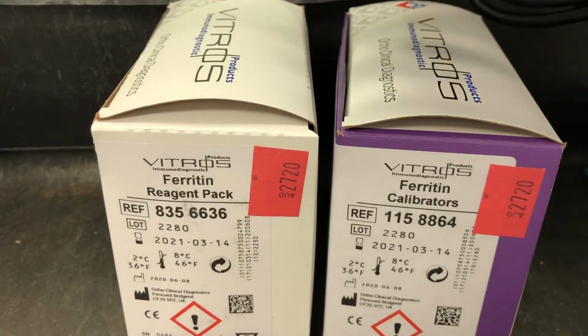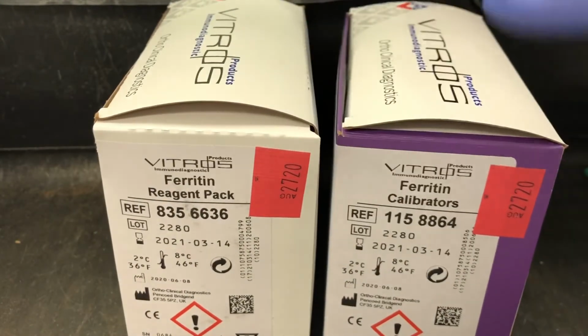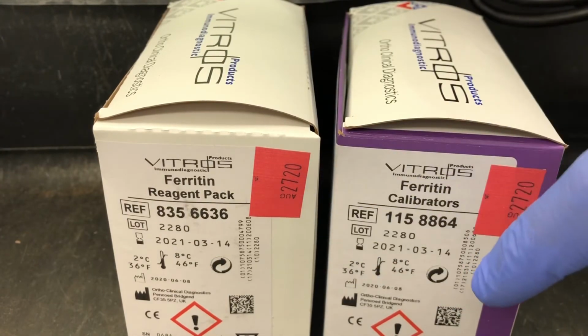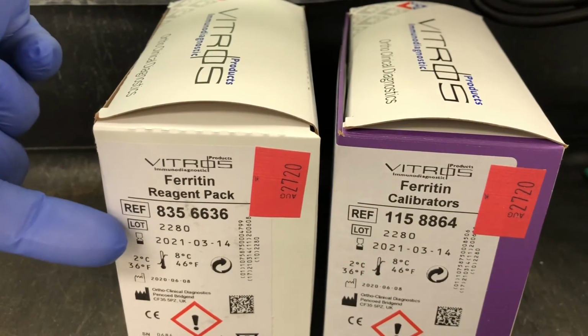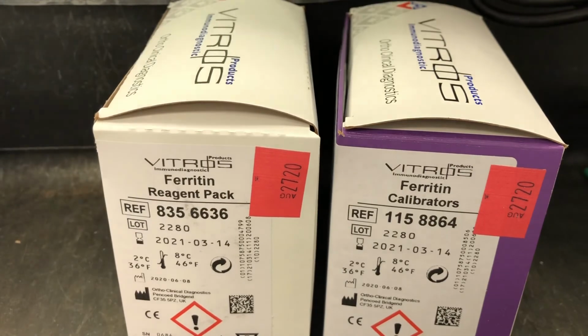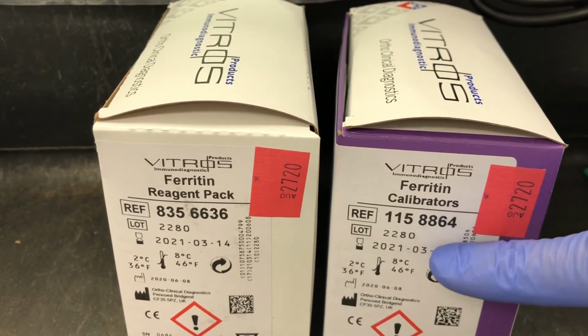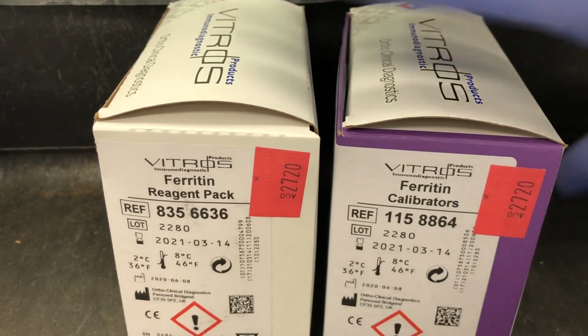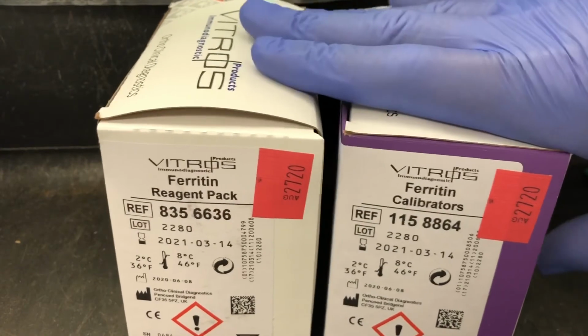For immunoassays, things are a little bit different. You don't have to order the calibrations. Once you load it, it'll tell you it needs to be calibrated, and then you just have to load the appropriate calibrator. Now, they are lot specific, so you just have to find the calibrator that matches the reagent pack lot, and that's how it works.